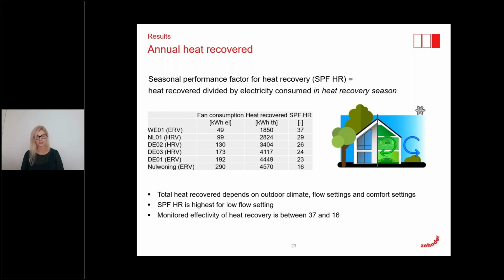quantity and the size of the energy that is used to provide a good indoor climate. What was measured during this time was also the fan consumption, and if we now look at the annual heat recovered, the heat recovered as thermal energy, to provide a comparison we can use a calculation similar to that for heat pumps, the coefficient of performance. We take the heat recovered and divide it by the fan consumption, the electricity that was used to provide this heat recovery. This we can call a seasonal performance factor for heat recovery.